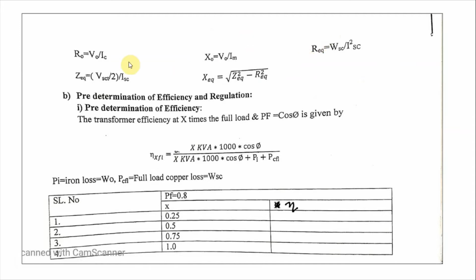Now using the SC readings, we calculate R equivalent and Z equivalent. R equivalent is calculated using the copper loss and the short circuit current, and Z equivalent is calculated using this expression. When we have both R equivalent and Z equivalent, X equivalent can be calculated using this expression. Coming to the predetermination of efficiency.